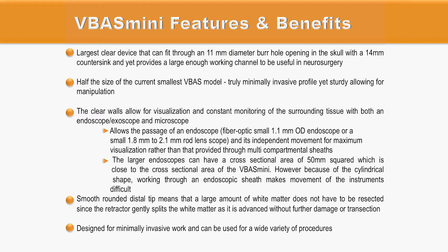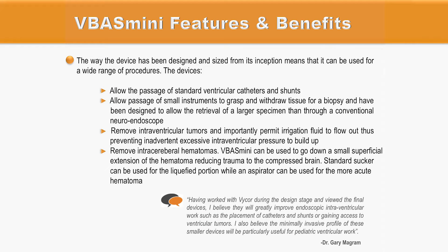It is a truly minimally invasive surgical device which can be used for a wide variety of procedures. The design of VBASmini offers clear advantages: it allows the passage of standard ventricular catheters and shunts, allows the passage of small instruments to grasp tissue for biopsy, and can be used to remove intraventricular tumors. Most importantly, it allows irrigation fluid to flow out, preventing excessive intraventricular pressure from building up.